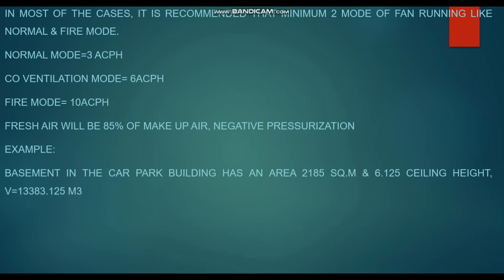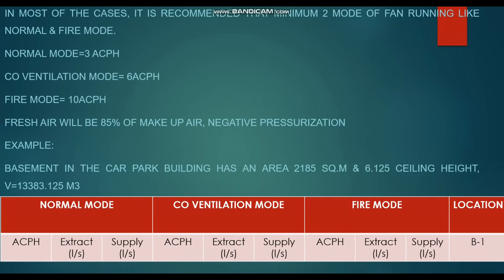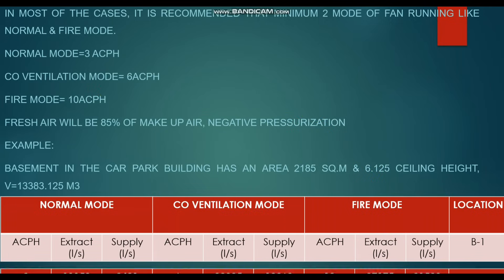Now we will see one simple example first before going into practical difficulties. For example, we have a basement car park with an area of 2,185 square meters and a ceiling height of 6.125 meters, giving a total volume of 13,383.125 cubic meters. We will calculate three operating modes: normal mode at 3 ACH, CO ventilation mode at 6 ACH, and fire mode at 10 ACH.